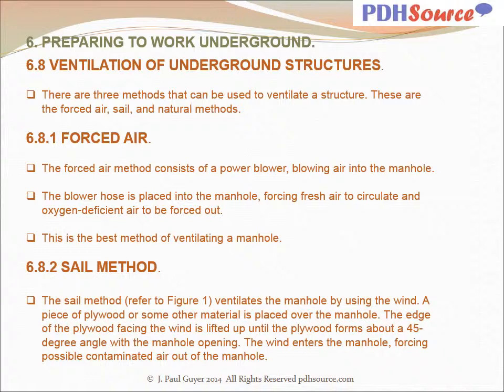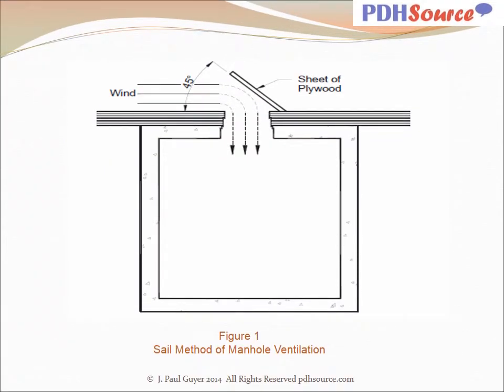The sail method ventilates the manhole by using the wind. A piece of plywood or some other material is placed over the manhole. The edge of the plywood facing the wind is lifted up until the plywood forms about a 45-degree angle with the manhole opening. The wind enters the manhole, forcing possible contaminated air out of the manhole. Figure 1 indicates the sail method of manhole ventilation.